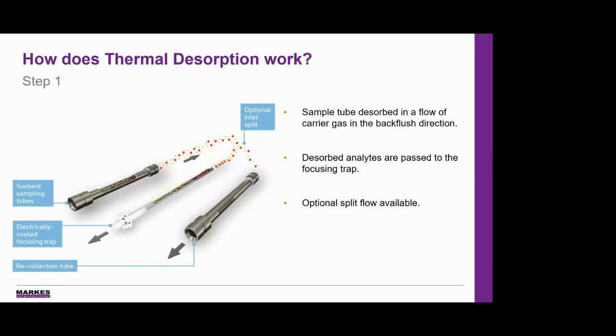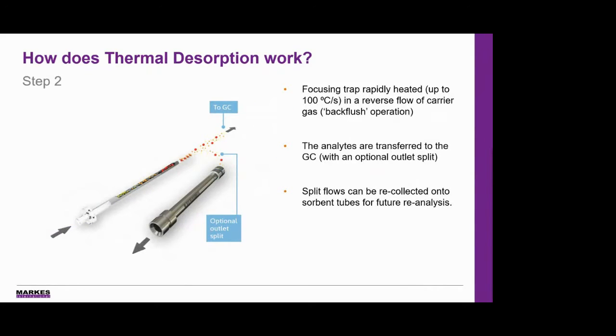During this stage, an optional split can be used for high concentration samples to reduce the concentration being introduced into the system. This optional split is recommended when performing direct desorption. During the second stage, the focusing trap is then rapidly heated at a rate of up to 100 degrees per second in a reverse flow of carrier gas — again a back flush operation. This enables the analytes to be transferred to the GC column as fast as possible for the sharpest chromatographic peaks. A split flow can also be used here for high concentration samples, and this also enables the recollection of samples onto sorbent tubes for archiving and future reanalysis.